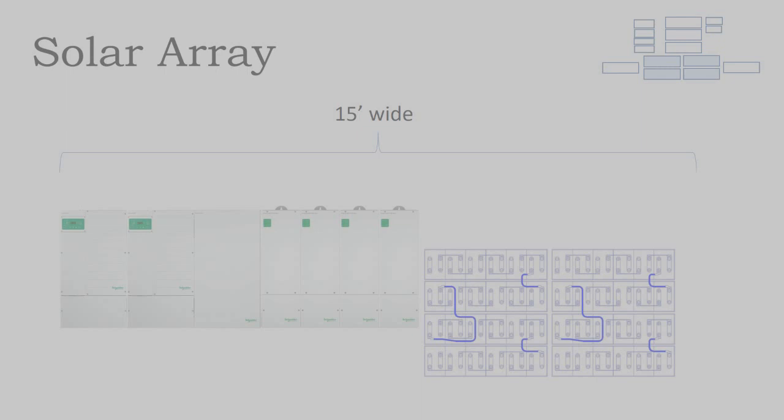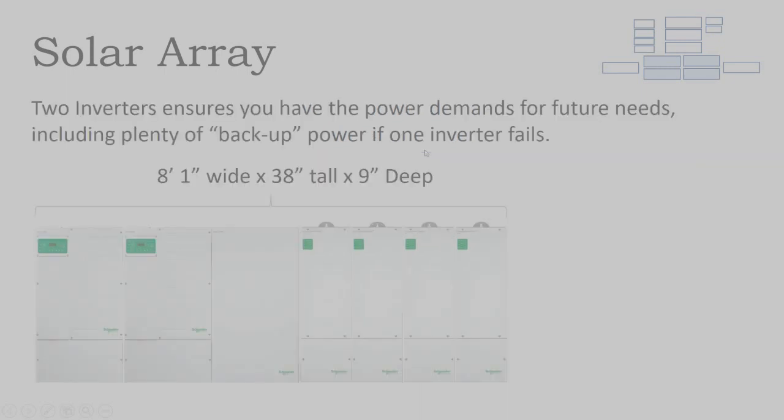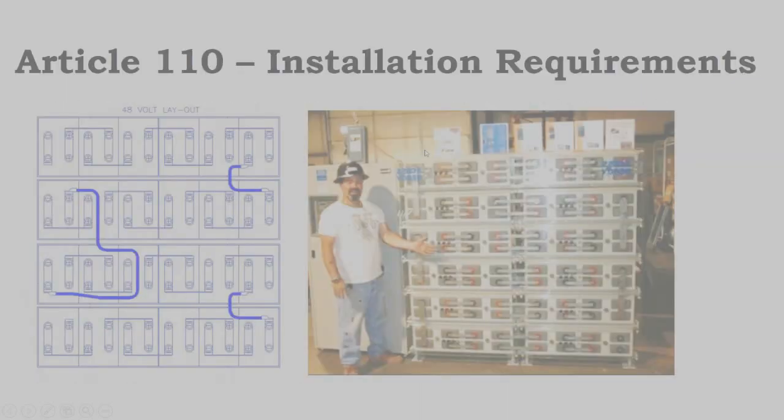So what we really need for a code-compliant room for the minimum space requirements of this electrical equipment is really a 16 or 17, actually an 18-foot wide room. And we don't have that.